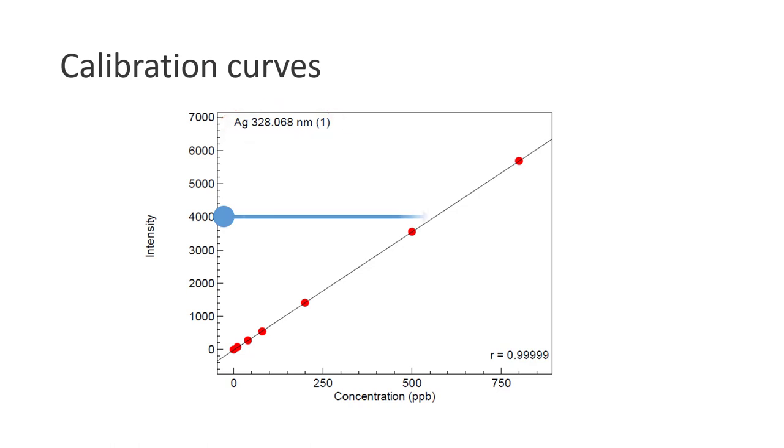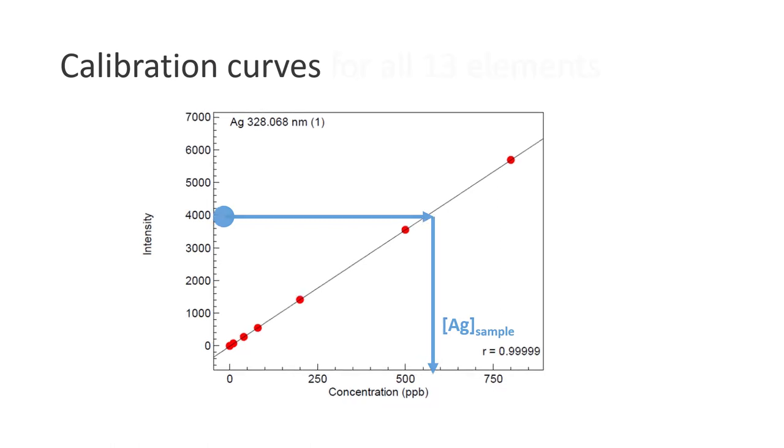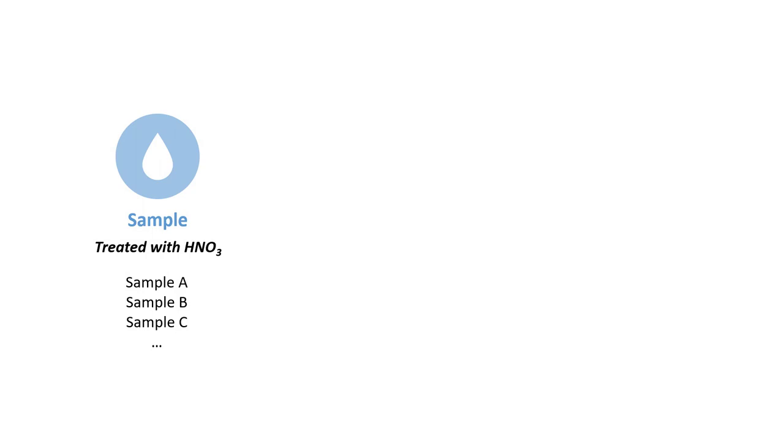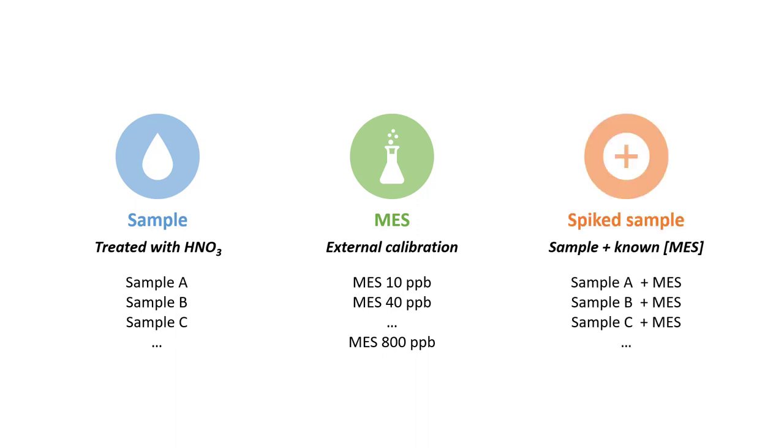For example, in this case of silver, if the emission intensity obtained at 328 nanometers is 4000 units, using the calibration curve we can back-calculate the concentration of silver present in the unknown sample. In this experiment we'll use the calibration curves of all 13 elements of interest. Don't worry about it, the software will help us plot these calibration curves automatically.